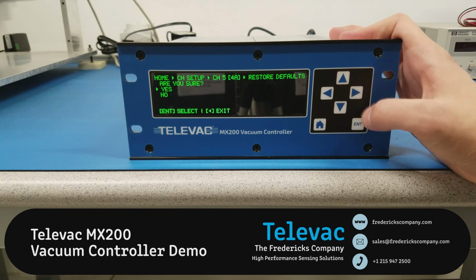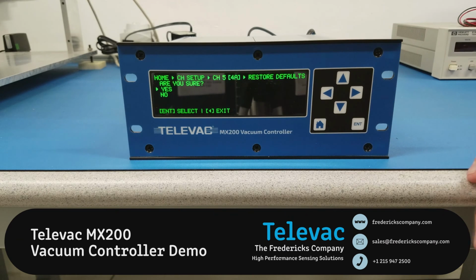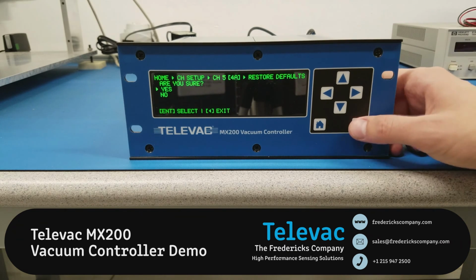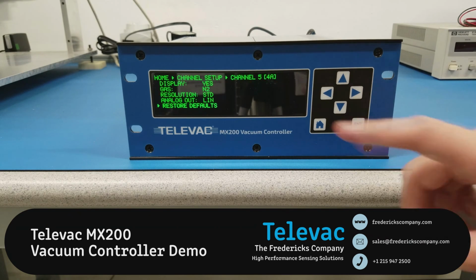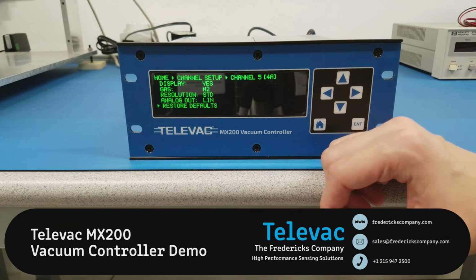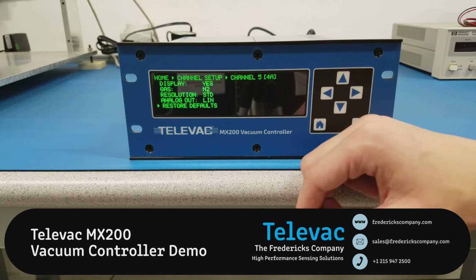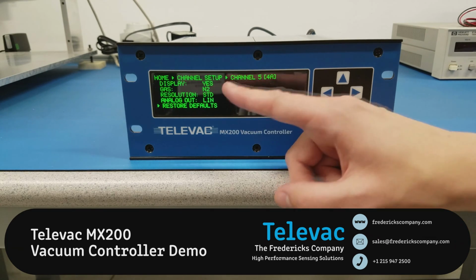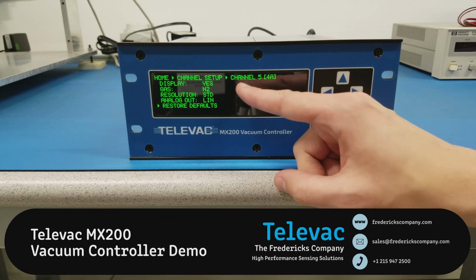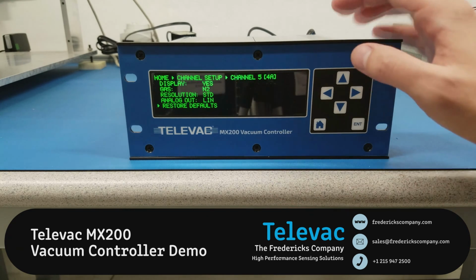Lastly, we can restore all defaults. So there's a check here just in case you accidentally enter this screen. So if you hit enter on yes, it's going to change everything back to the standards for this sensor. So for the 4A, it's displaying, the gas is nitrogen or air, resolution is standard, and analog output is linear.